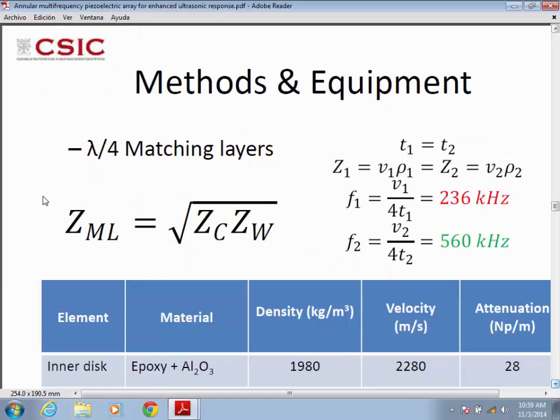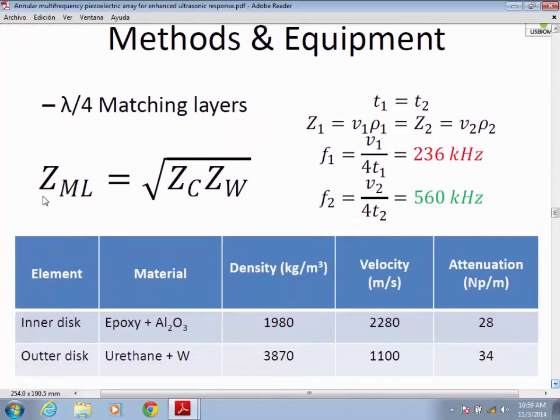So the next phase is to have these matching layers. So we're using this equation. We want to match the impedance of the water, so we design two different layers because we have two different resonant frequencies for the two regions of the transducers. In order to get these two different layers, we're using two different materials. One layer is made with an epoxy and an alumina addition. Then we get this speed of propagation of sound. And the other outer disc is using urethane with some wolfram addings, and we get another speed, because we want the same thickness in both layers in order to have a radiant surface that is almost flat.